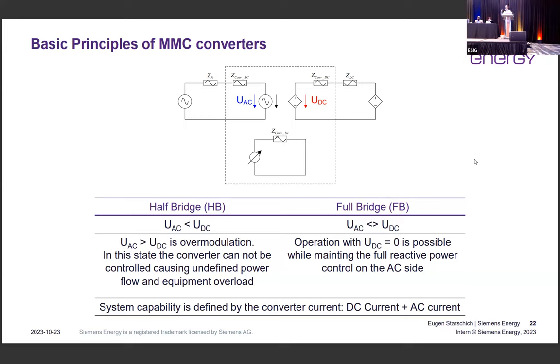The AC side is defined by the AC grid codes. In Europe, they are very specific HVDC grid codes. The same is now happening in the US, where the grid codes are being developed. So if we look at how this AC source is behaving, it's defined more or less by the AC grid code. Looking at the DC side, this is what we as an industry are working on right now, to also define the grid code for the DC grid.